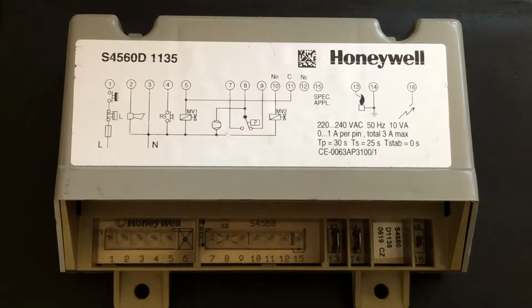Number 4 is a reset, which means that if the flame fails, the system will go into fault mode and will trigger an alarm. So to have this running, you have to make a short circuit between number 4 and the neutral. Usually you'll have a switch for that. It's a momentary push button. If you move further, you will see there's a fan sign which links to number 8.